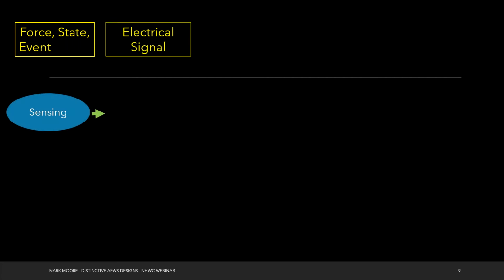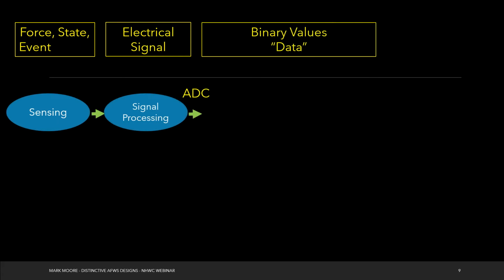So when we're talking about measuring stuff with calibrations, the first thing you have is some sort of force, a state, or an event. It could be a tipping bucket that tips, or realistically, it's rainfall that falls from the sky or water level that goes up. And we sense that. But we can't just say it rained. We have to turn that into some sort of electrical signal. And so that happens through signal processing. With a tipping bucket, it might be a magnet across a reed switch. With a PT, that might be changing that force, that pressure, into a voltage. Then we want to actually see what happened. So we have to convert it back into something digital that our data loggers can read. And that's where that analog to digital converter comes in.